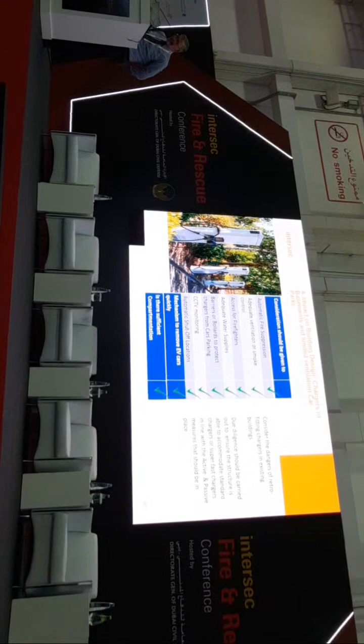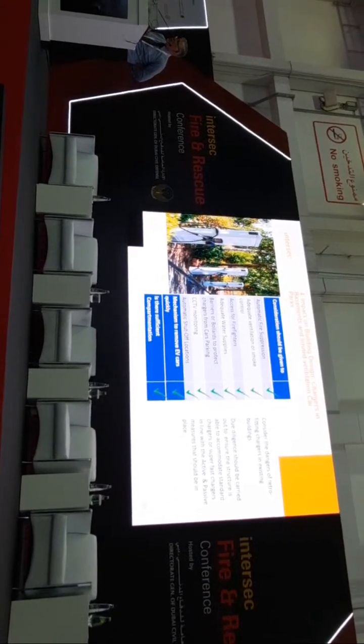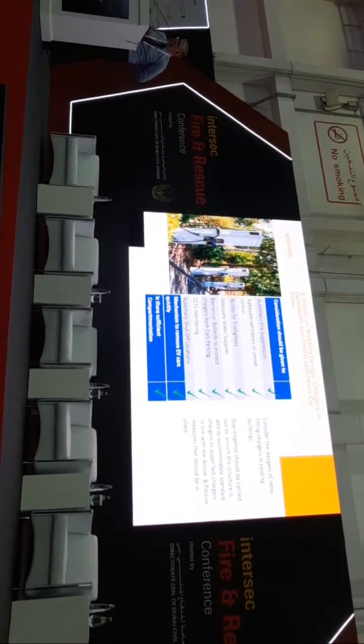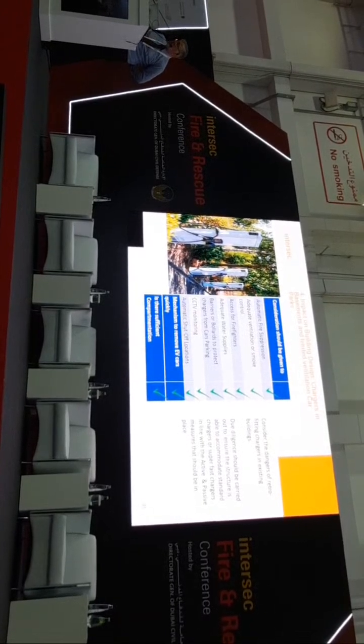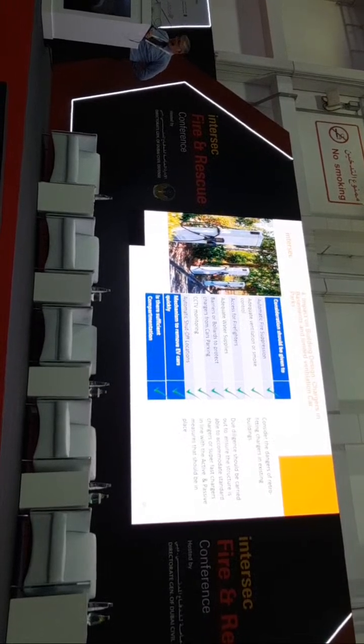You need adequate supplies in place: good automatic fire suppression, adequate ventilation or smoke control depending on the setup, access for firefighters, adequate water supply, barriers to protect the chargers so nobody hits them, good CCTV monitoring as an option, and definitely automatic shut-off.